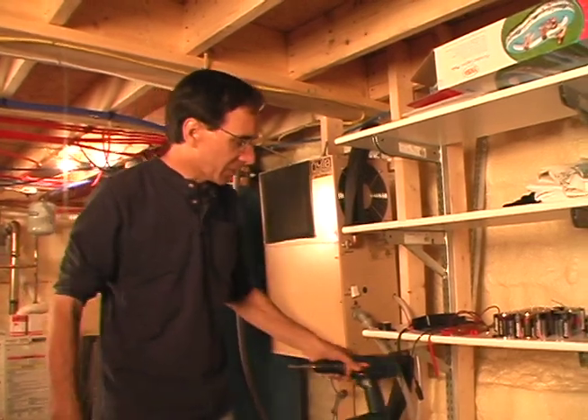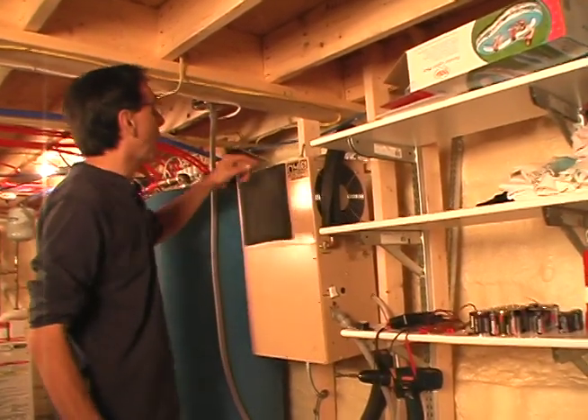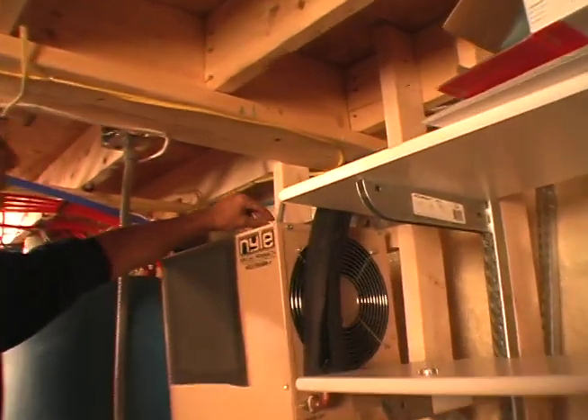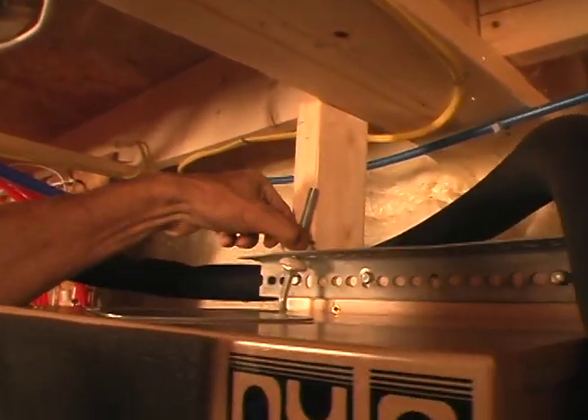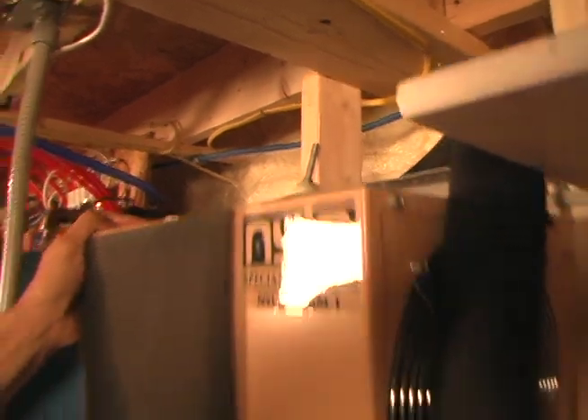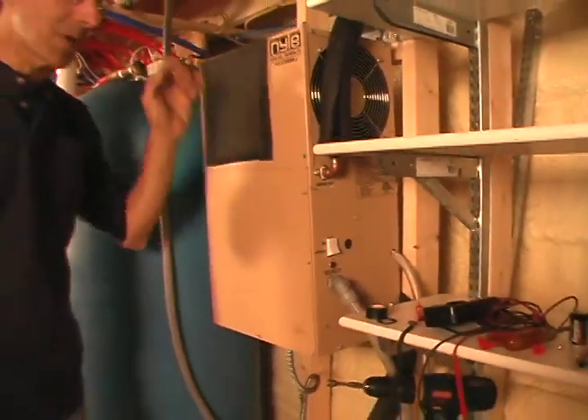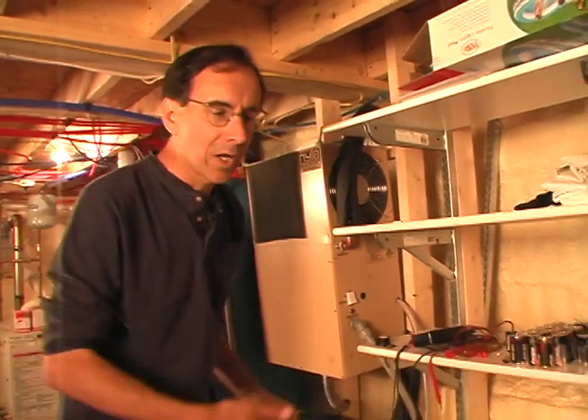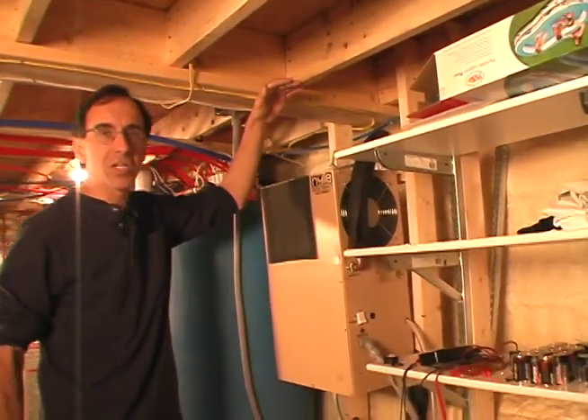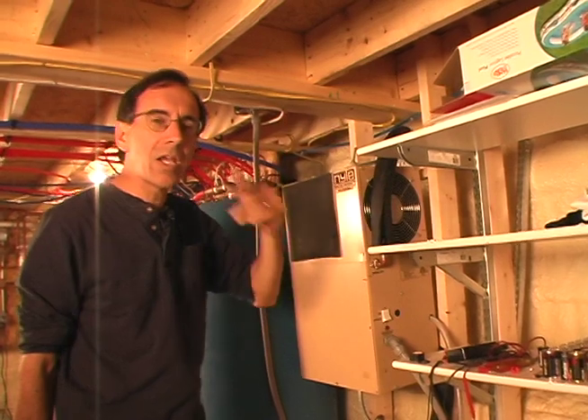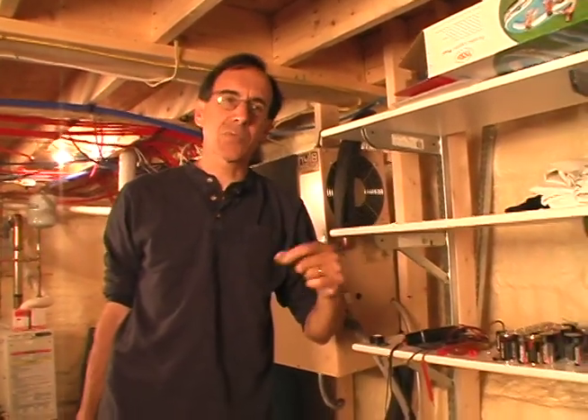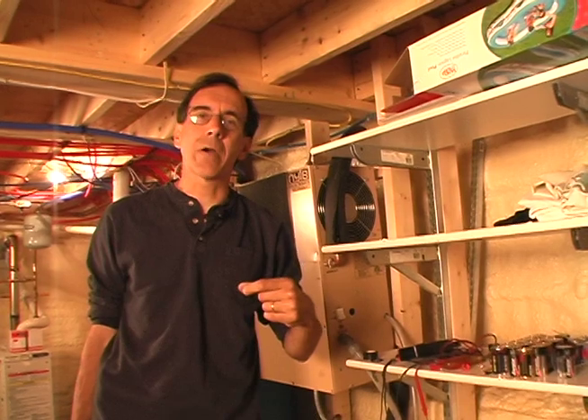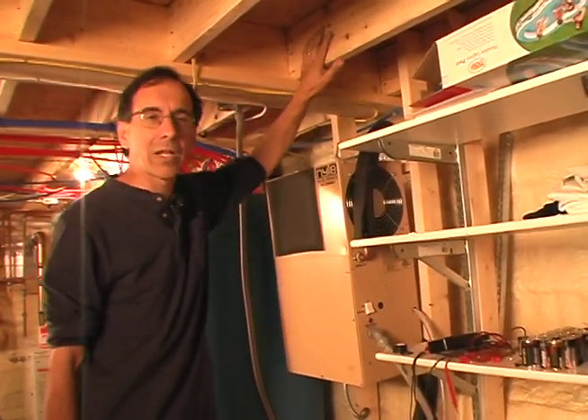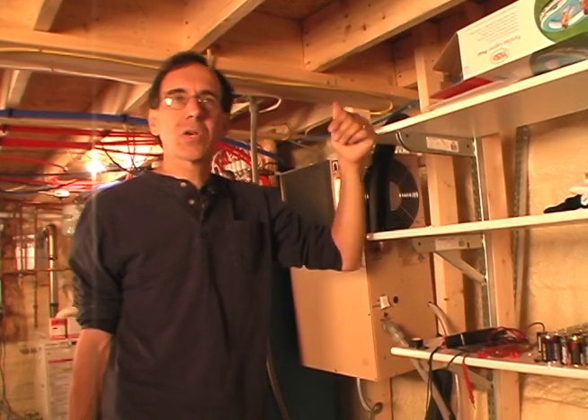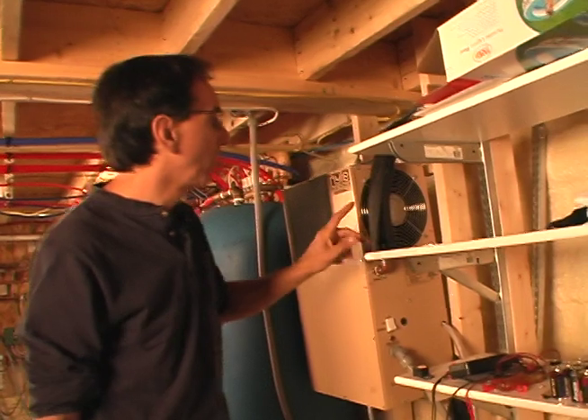A couple of things we've got going on here. One is this is mounted resiliently in that we have rubber donuts here, and the unit is floating because it does make some noise. It could sit right on the floor, but I don't want it right on the floor. I wanted it up near the ceiling where it's going to get the warmest air. A heat pump likes to have as warm air as possible to make hot water, so up closer to the ceiling is warmer. If we wanted to try to extract warm air from upstairs, maybe if the wood stove was running or something, we could vent upstairs.